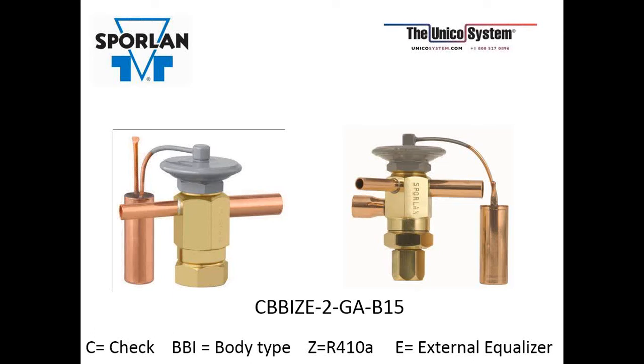And then the GA is our thermostatic element used for heat pumps and air conditioning applications. And then some valves will have a bleed port, indicated by the letter B at the end and then a number, like in our example, B15. So this indicates it has a 15% bleed. This allows the system to bleed back through the valve, bypassing the pin port, to equalize the pressure during the off-cycle, very much like a cap tube system. The bleed port can be a drilled passageway through the valve body, or it could be a machined notch in the seat that allows a controlled amount of seat leakage. This 15% bleed also increases the capacity by 15%, since it is a continuous passageway with no way to close it off.